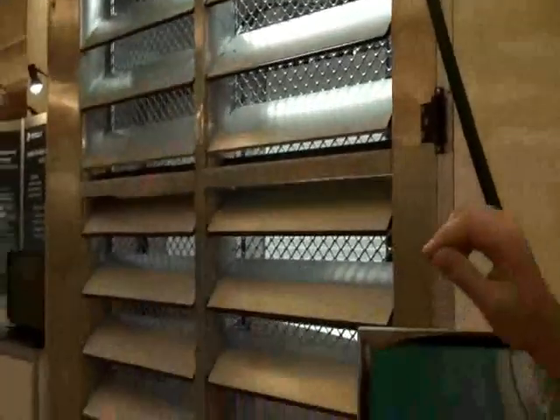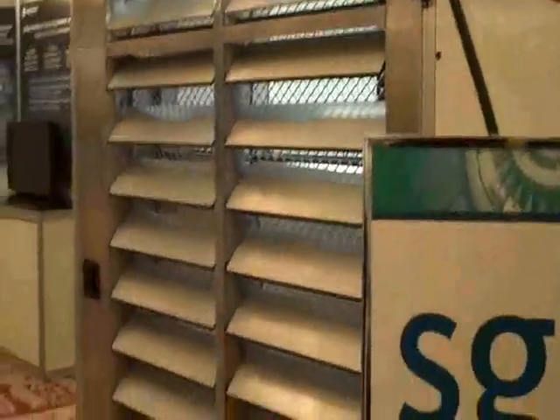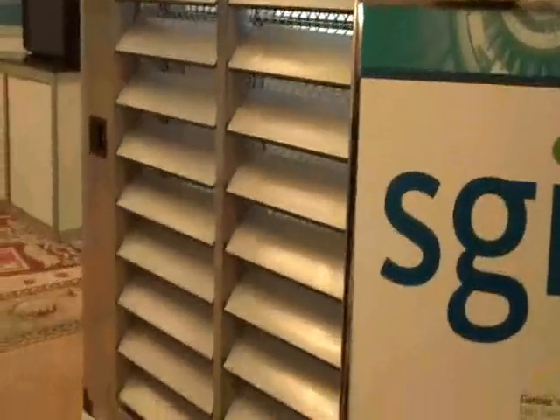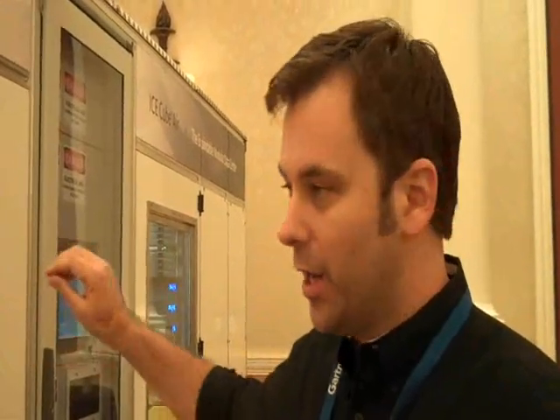It's a single pass system. So the air enters this way in a positive pressure and passes all the way through the system. When we go inside, you'll see where the air comes in and where the fans are and how that relates to where the servers and the racks are, and how air enters and leaves the unit through the other side. We're also going to talk about a couple of different global ambient temperature and humidity conditions and how the control system uses even the server's own heated air to bring it back around and keep the servers warm in cold climates. So I'm going to walk this way. Sounds good.